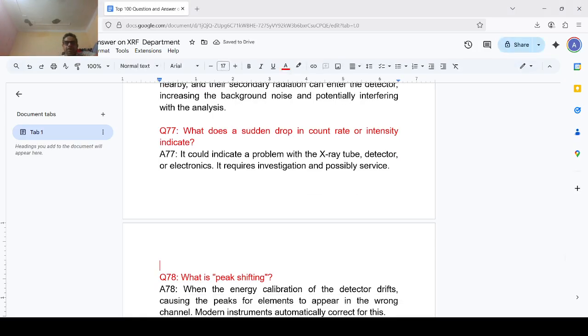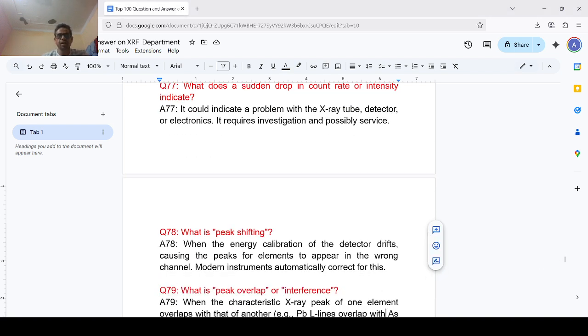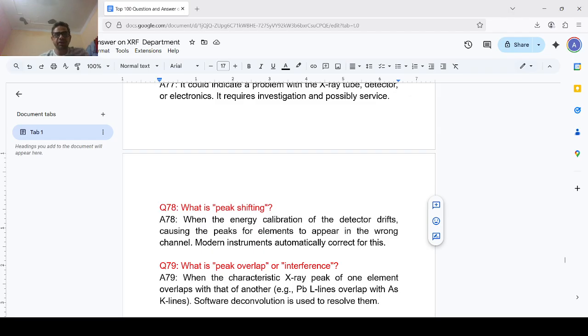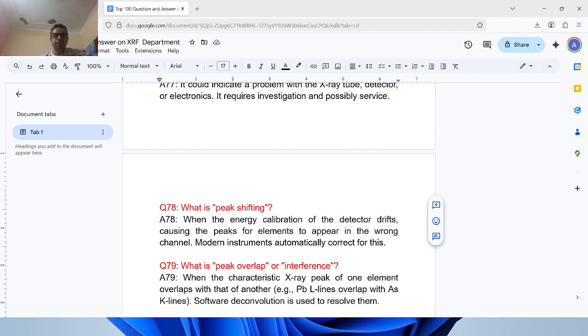Question number 77. What does a sudden drop in count rate or intensity indicate? It could indicate a problem with the X-ray tube, detector, or electronics. It requires investigation and possibly service. Question number 78. What is peak shifting? When the energy calibration of the detector drifts, causing the peak of the element to appear in the wrong channel. Modern instruments automatically correct it.